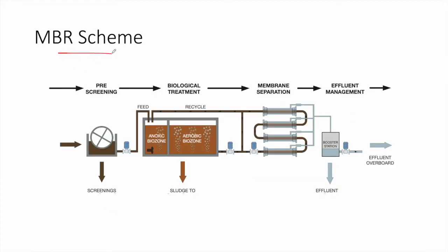Regarding the MBR scheme, we always start by pre-screening. The screening process is very crucial in an MBR wastewater treatment plant. We use fine screening and must highly reduce suspended solids — reduce the TSS — otherwise we will face clogging problems in the membrane separation.